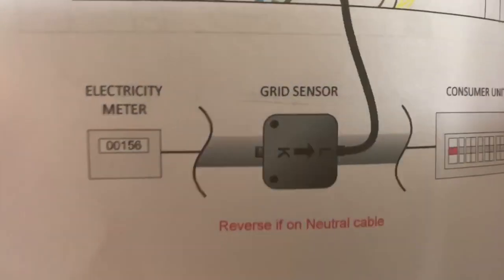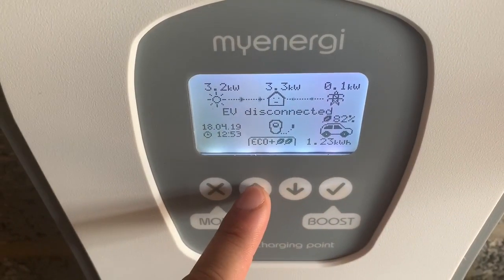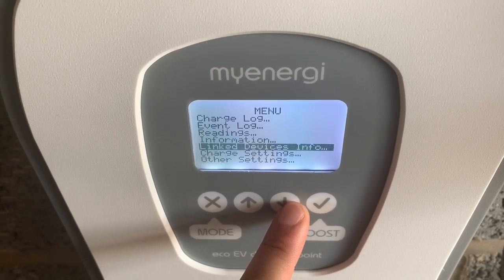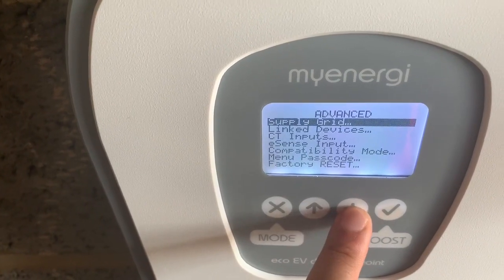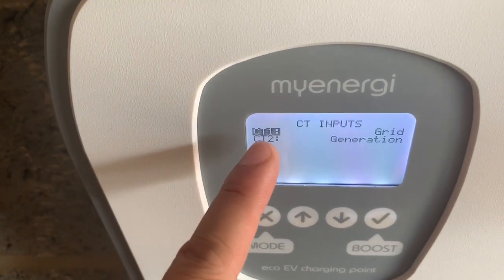The zappi manual shows you the orientation of the CT clamp — where you clamp it on in between the grid and the consumer unit. The important thing you need to know is when you go into the settings, go into other settings, then into advanced, and type in your password. Then go to the CT inputs — if you're placing a second CT clamp, you have to tell the unit, so go into the CT clamp setting and select which input you need: in this case, PV generation, load, storage, or off.